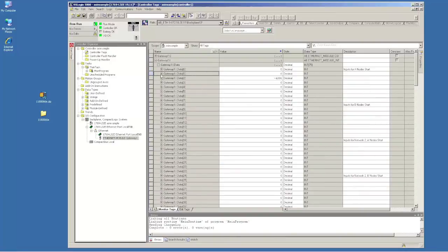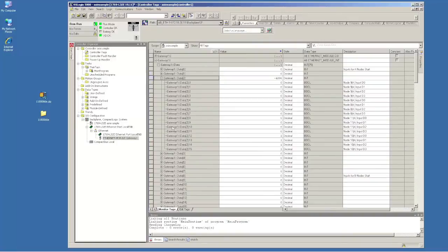I have my e-stop. I just want to show you one I/O. E-stop at node 10. I think it's in word 2 here. Okay, so input data. If you notice, it says node 10 right here. My e-stop is 1111. That tells you that it's pulled up. And when I press the e-stop, you can see that all the ones go to 0. It's telling you that the e-stop has been pressed, and you can send someone out in maintenance and maybe take a look at it. That's all there is to it, to configure the AS interface gateway.